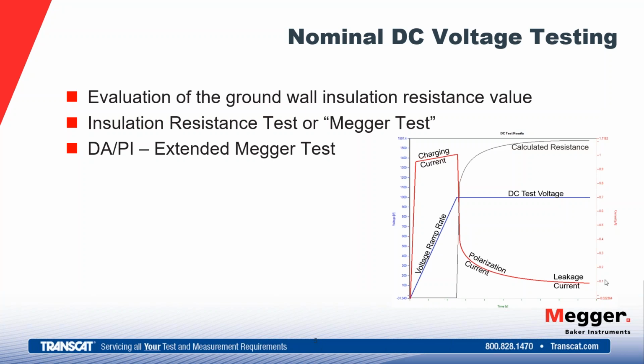minute. And then we're going to read that value, the current value that we're reading at the end of 1 minute. We know the voltage, so we take the voltage divided by our current and arrive at the resistance value. And then we're going to temperature correct that value so that we can compare it to a minimum value. So again, this test itself lasts for a minute, and if we were to hold voltage on and continue the test after that 1 minute, then we move into the DA or the PI, which is basically an extended Megger test.